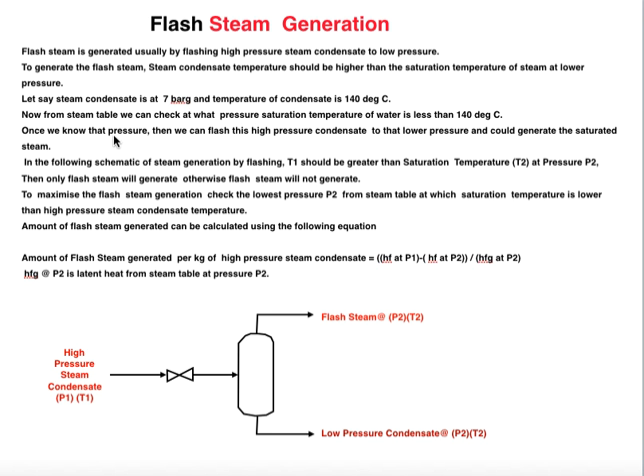Once we know P2, we can flash the high pressure condensate to that lower pressure and generate saturated steam. To maximize flash steam generation, we should check the lowest pressure P2 from the steam table at which the saturation temperature is lower than the high pressure condensate temperature. By choosing a lower P2, the steam is maximally flashed and more flash steam is produced.